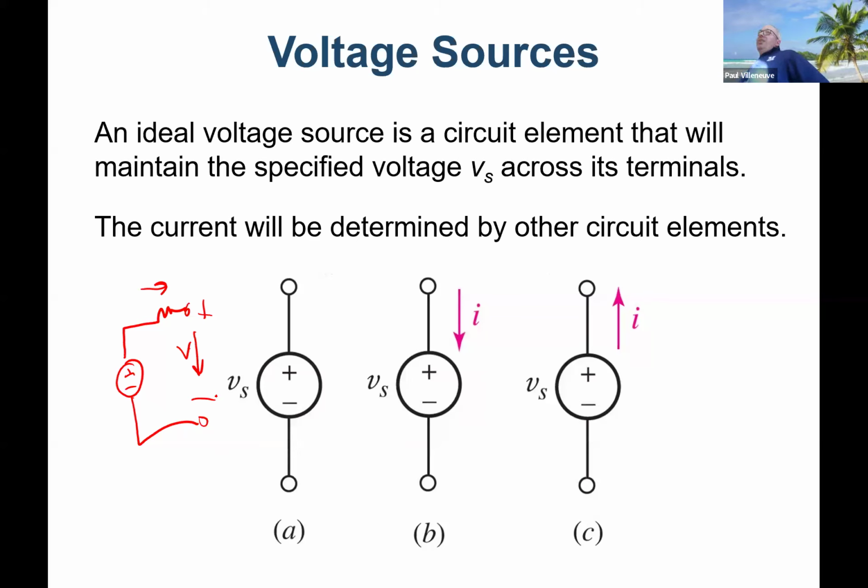And this happens all the time. If you look at the utility system, which can do hundreds of thousands of amps, all these individual generators, you can model them as an equivalent impedance with a voltage. Like on campus, you can look at the Versant power system coming in, and there's a voltage and an impedance in series with that voltage. And that's how you can calculate different parameters on it.